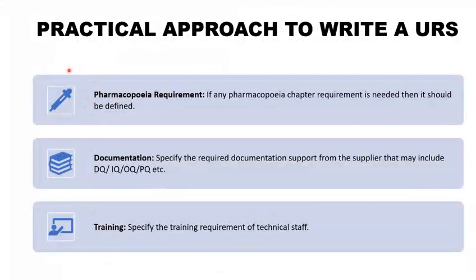Next is pharmacopoeia requirements — if any pharmacopoeia chapter requirement is needed, it should be defined. Next is documentation — specify the required documentation support from the supplier, which may include DQ, IQ, OQ, or any other deliverables and test scripts. Finally, training — specify the training requirements for technical staff, including detailed practical and theoretical knowledge to be provided to end users.